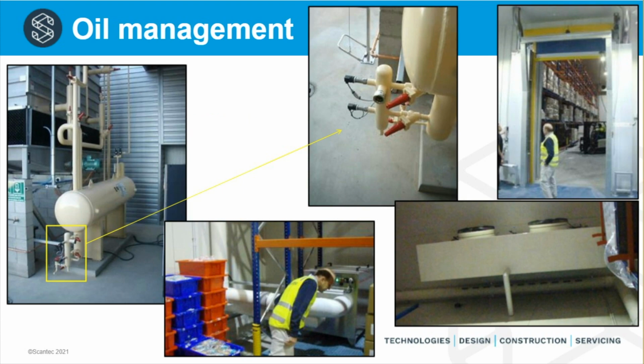This slide shows a little bit more than oil management. You can also see a couple of pictures there, one down the bottom where the guy is bending over a bit. That shows a dehumidifier, which is used to reduce the impact of infiltration into the cold store. The same in the top right-hand picture. There you see a horizontal air curtain, which is used for the same purpose, in other words, to minimize the amount of infiltration that goes into the cold store.